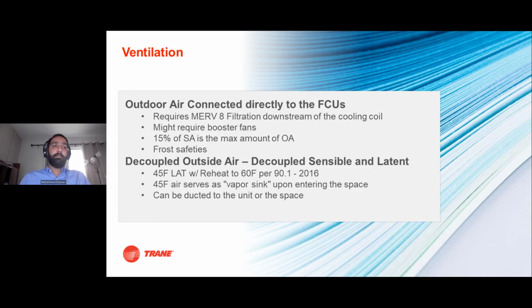Ventilation is a big topic around VRF systems. Typically, raw outside air can be delivered directly to the fan coils, but this does require MERV 8 filtration downstream of the cooling coil, because this does result in latent work being done at the cooling coil. It's important to remember that especially the ductless style of indoor units are static neutral. That is, they will not pull in any outside air. So booster fans are typically required for this kind of application. It's also important to remember that there are frost safeties on these indoor units. So, if it's very cold outside, say it's 0 degrees outside in Boston, and you're delivering 50 to 80 CFM of air to the indoor unit, even that small quantity can push the mixed air temperature below the frost safety on extreme days.